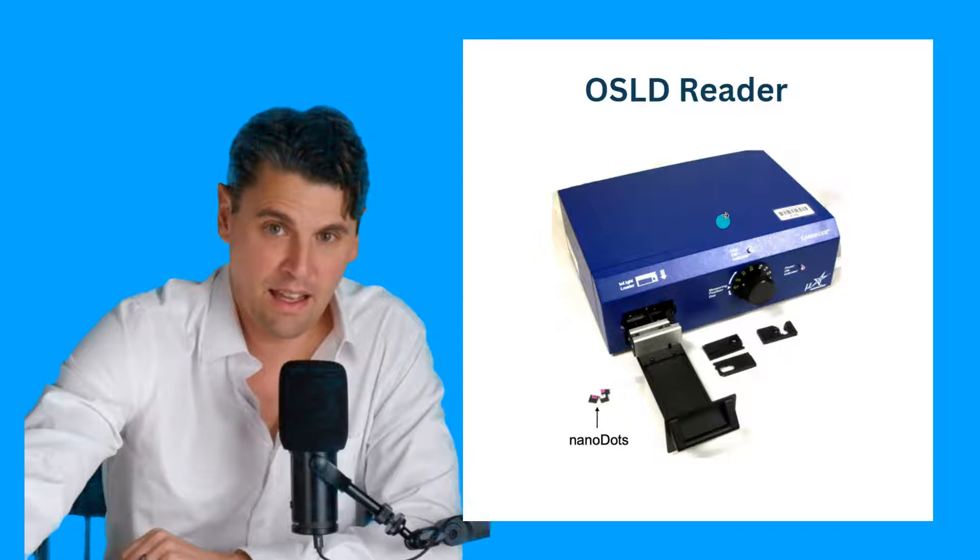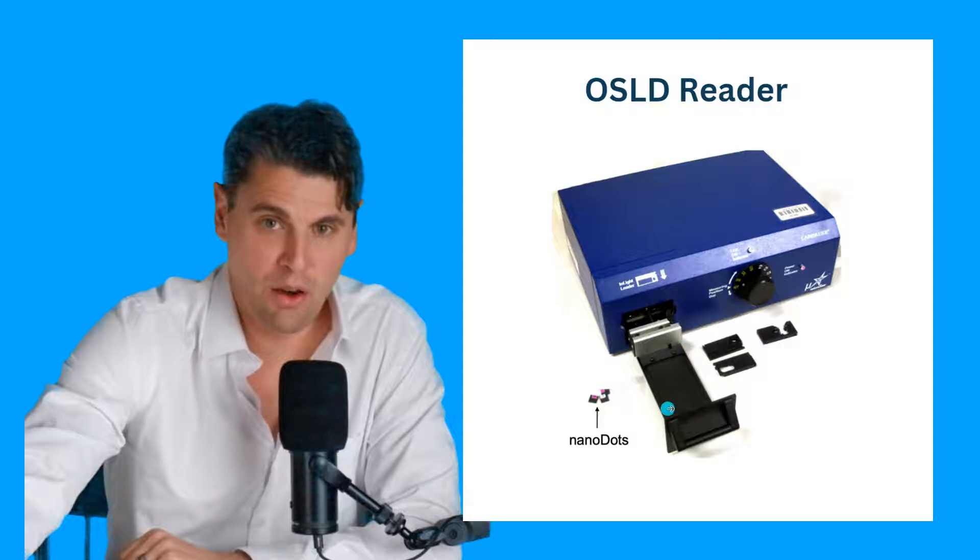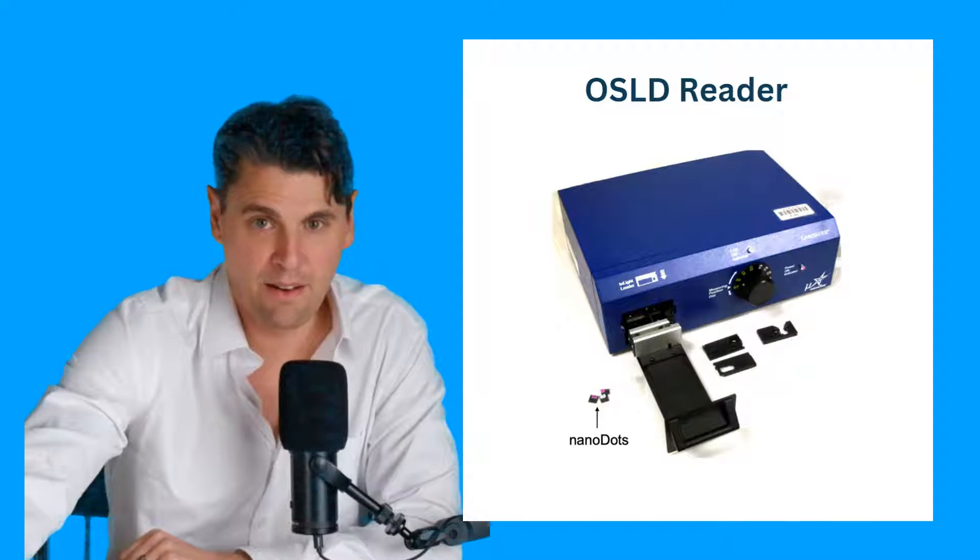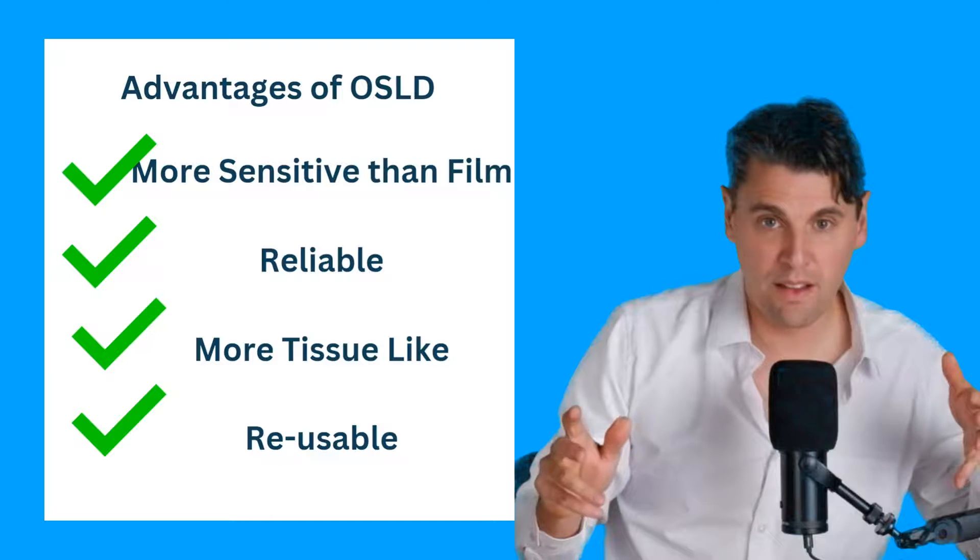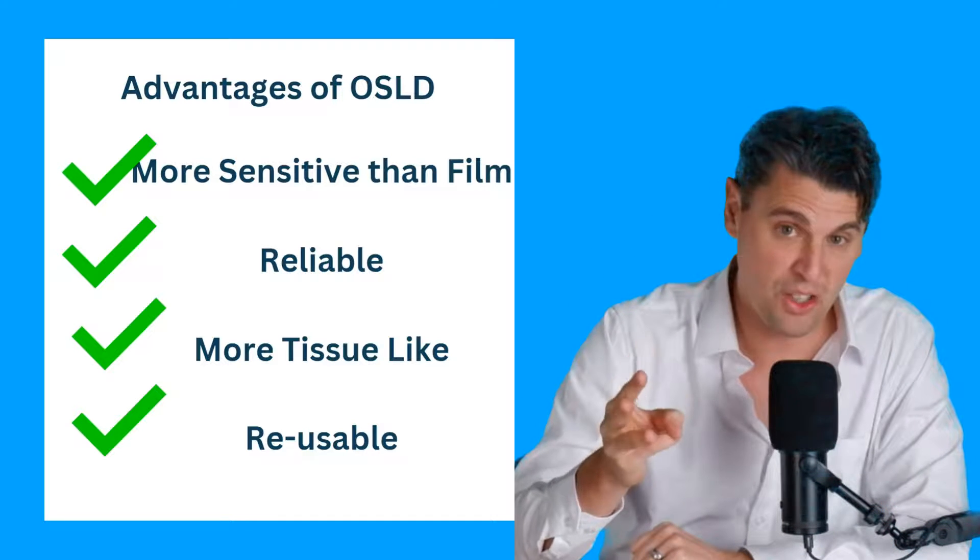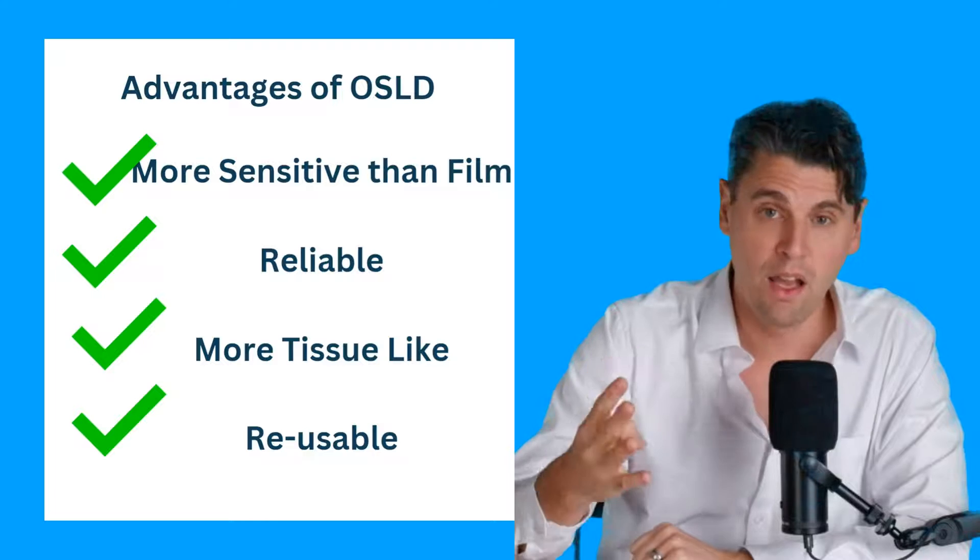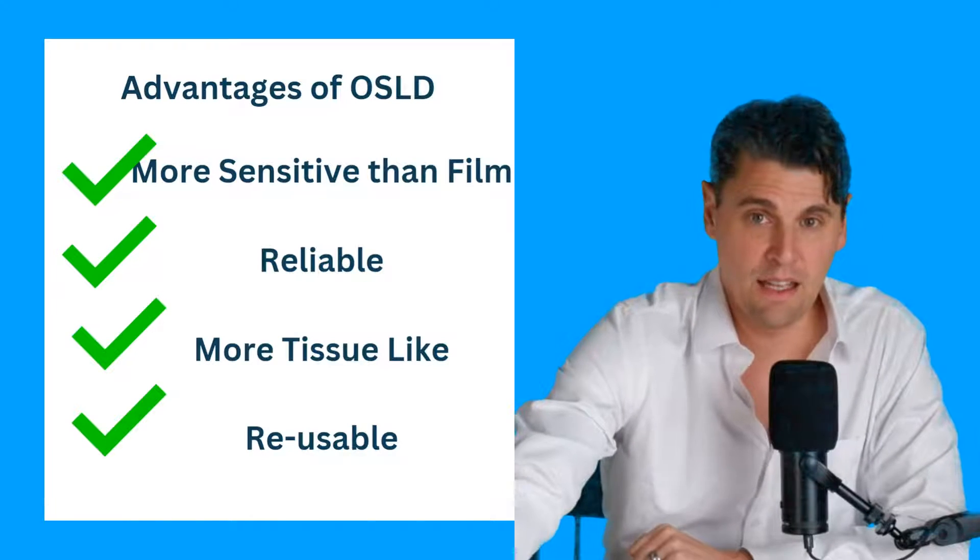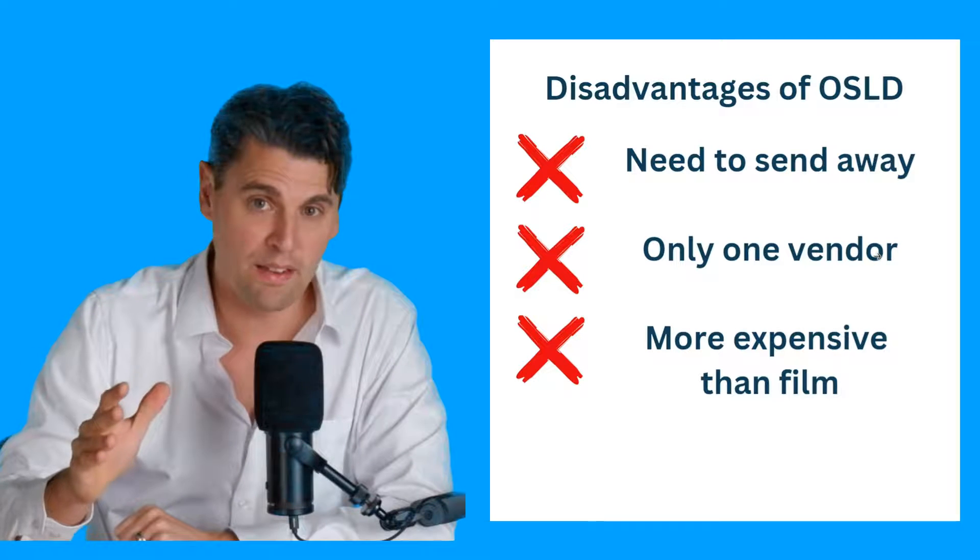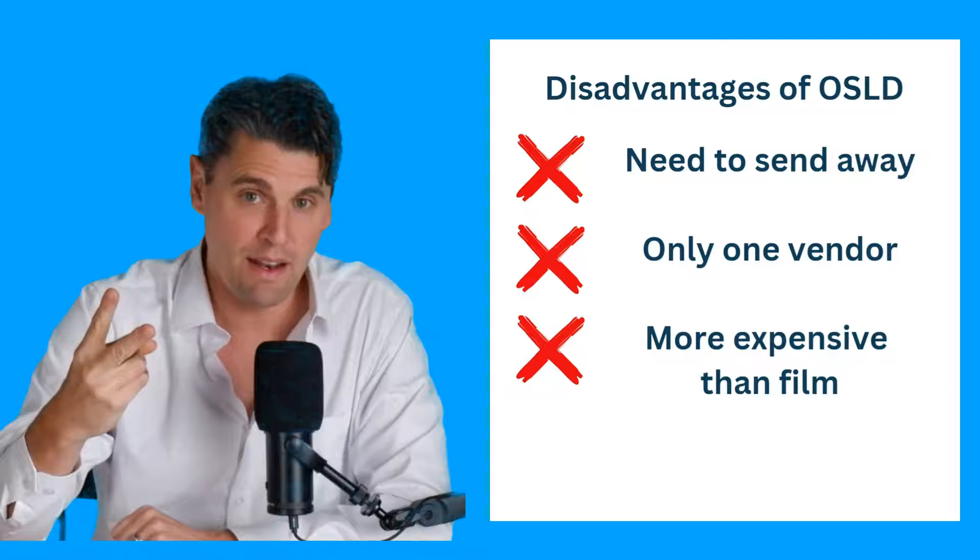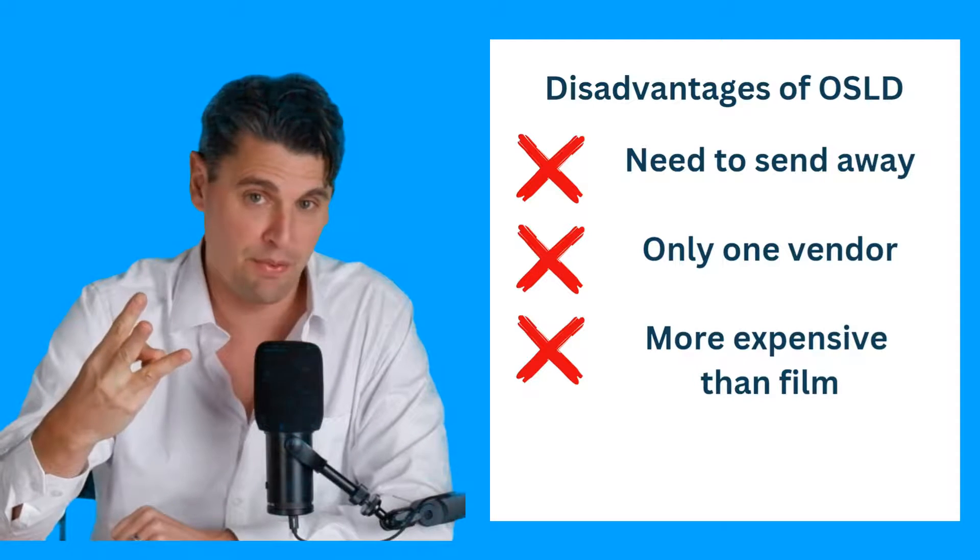Advantages of OSLDs, more sensitive than film, reliable, more tissue-like than film as well. Also, more reusable than a TLD. Disadvantages of OSLD, you need to send it away still. There's only one vendor as of now, and it's more expensive than film.